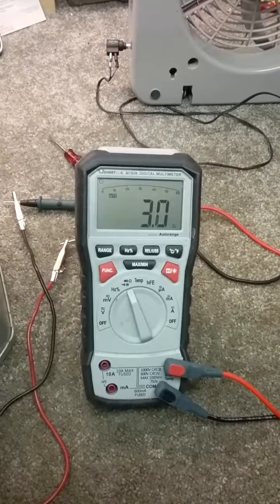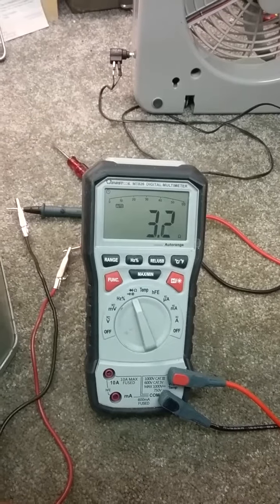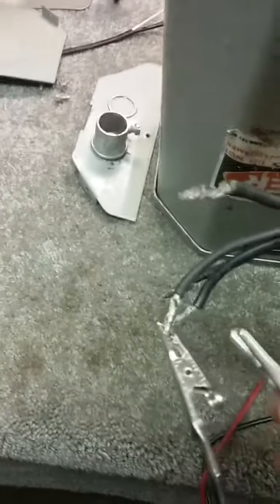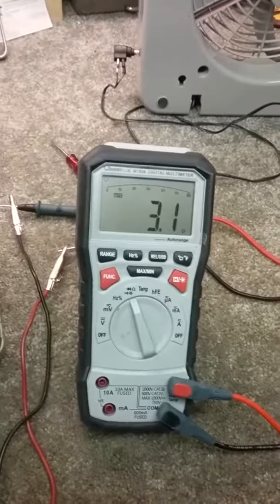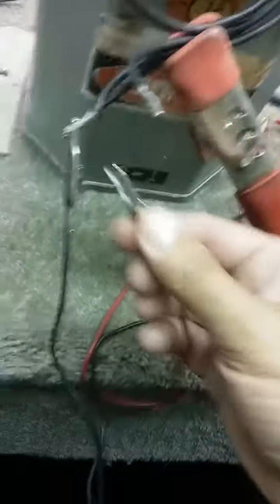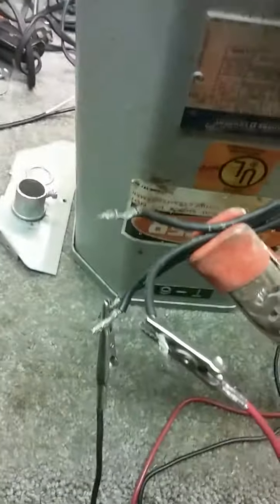Okay, and it's jumping around 3 ohms, which is, I would imagine, about right. And we'll check the next coil here. And I'm taking care that though these are close, they're not touching. Okay. And on that one we got 3.2 ohms, 3.1 ohms. So both coils seem fine on the secondary of the transformer. Now I'll do the same check for a short between the two coils on the secondary, and we have no resistance, or zero load, overload. So there's no short.